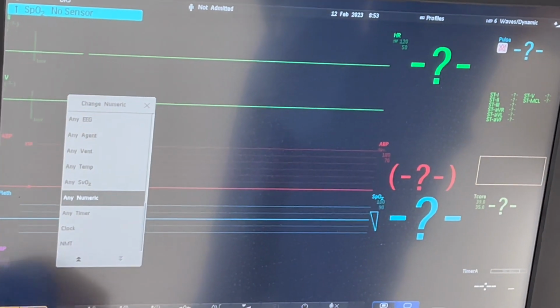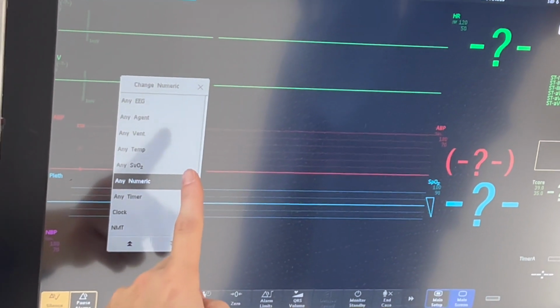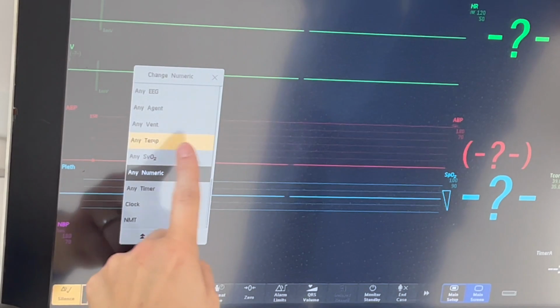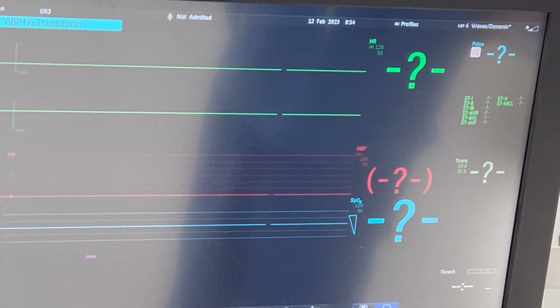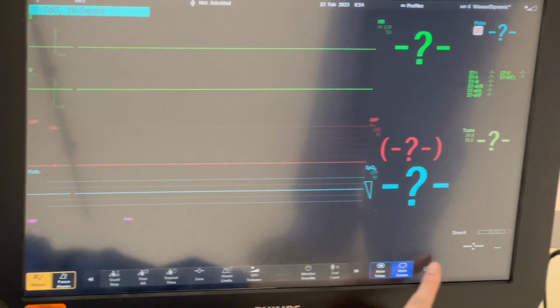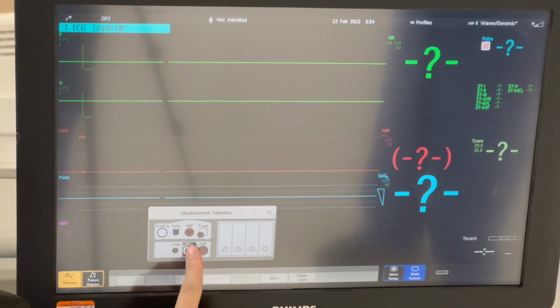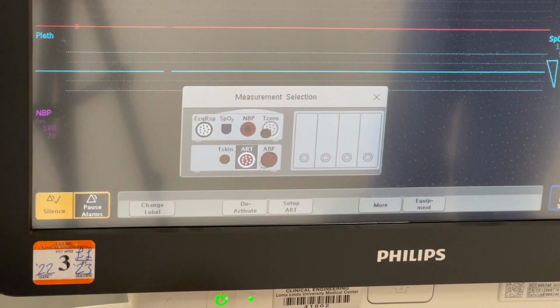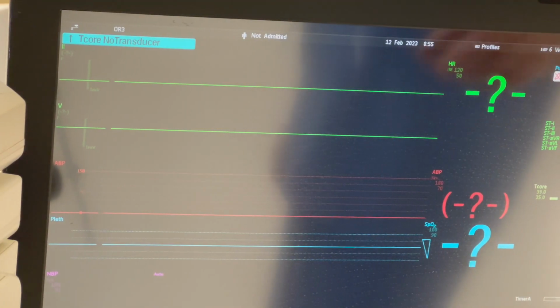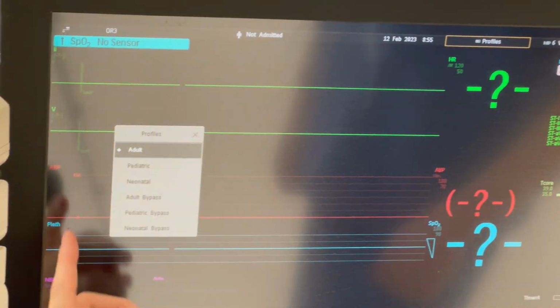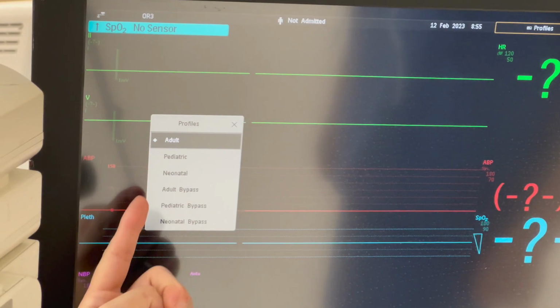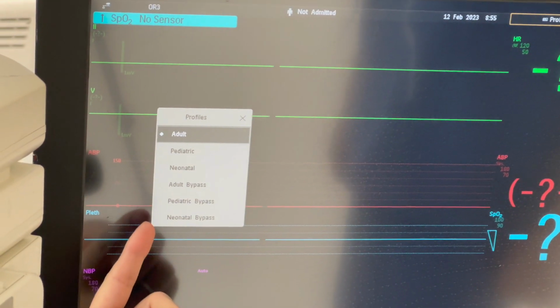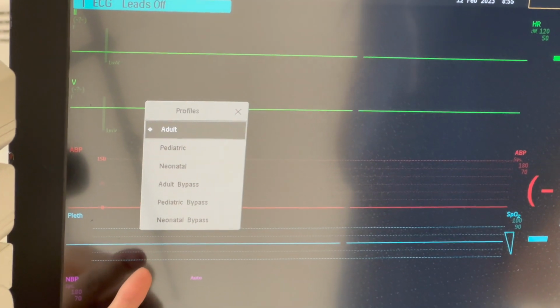If you need another parameter to show, you can click an empty box like shown, and you can add temperature in, for example. And if you're trying to activate the art line, you may need to click the little box in the lower right corner, hit the art line, and then hit activate. If you're doing a pediatric case, for example, you'll want to switch from adult to pediatric profiles, and then again, make sure your monitors and alarms all match appropriately.